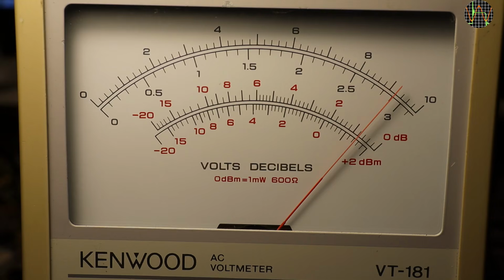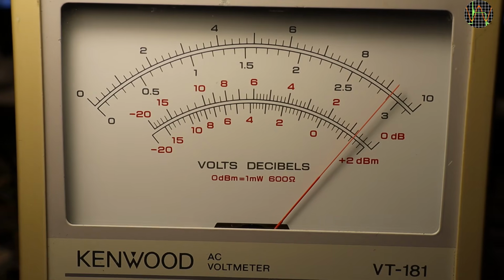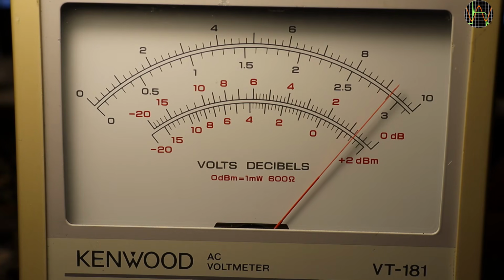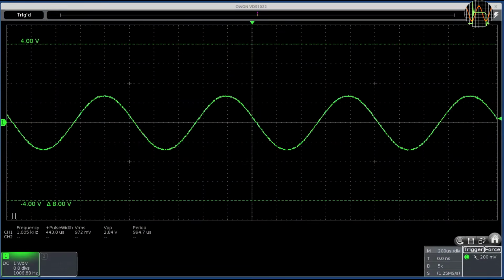Sorry for the flicker caused by the interaction of the pulse width modulation of my torchlight and the camera shutter. The top 2 cal positions are trim pots. The lowest one is a trim capacitor. The first cal step requires applying a 300 mV RMS sinusoidal signal at 1 kHz to the VT-181 in the 300 mV range and adjusting VR102 so that the needle is on 3. From my position directly in front of the meter it is, but maybe slightly off for the camera positioned a little sideways. At the same time, the amplifier output needs to be checked with a scope that it doesn't clip.